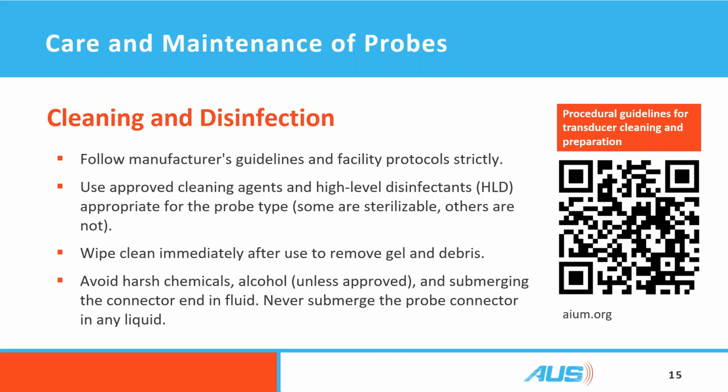infections and so on. So use approved cleaning agents and high-level disinfectants appropriate for the probe type, meaning, again, each manufacturer has a chart, has guidelines to what disinfectants should be used or should not be used. Some need to be sterilized, others don't.